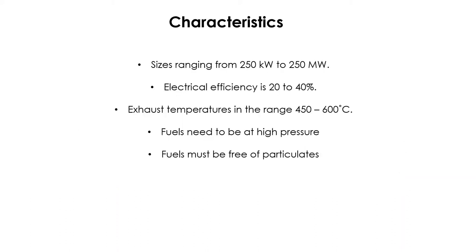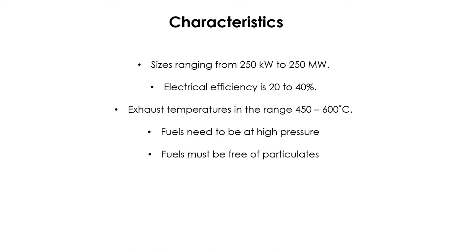The typical characteristics of gas turbines: the size is restricted to a standard frame size, ranging from 250 kW to 250 MW. In microturbines, the size can range from 25 kW to 500 kW. The electrical efficiency is 20 to 40%, and can be increased up to 50% for designs with cooled turbine blades.